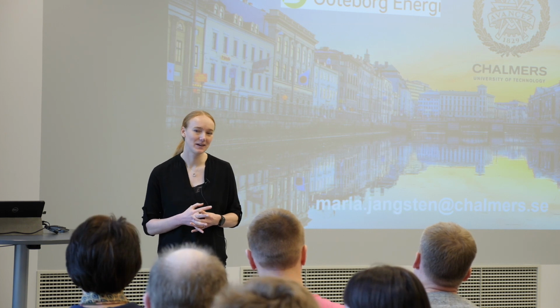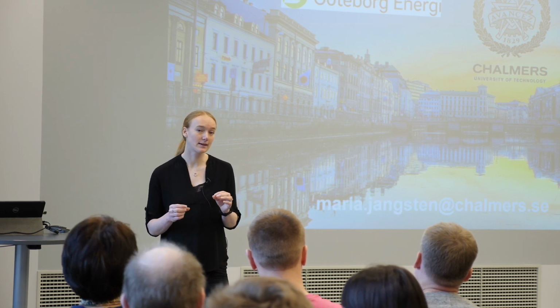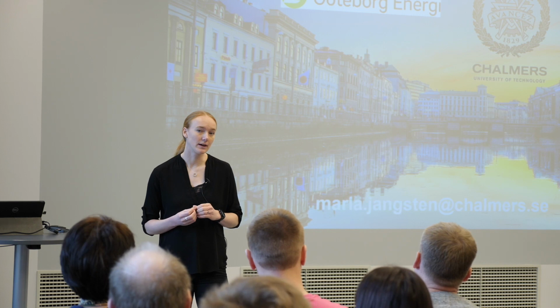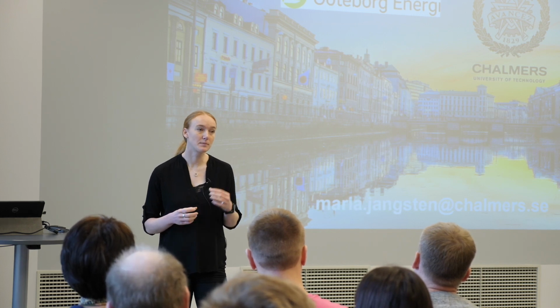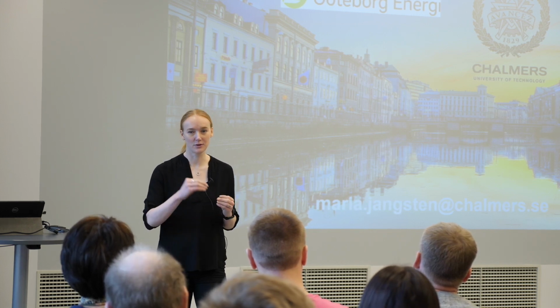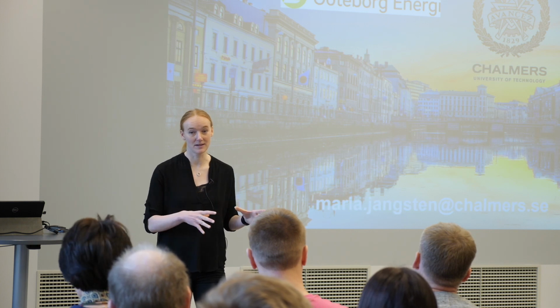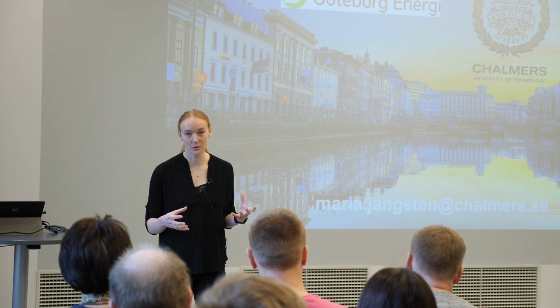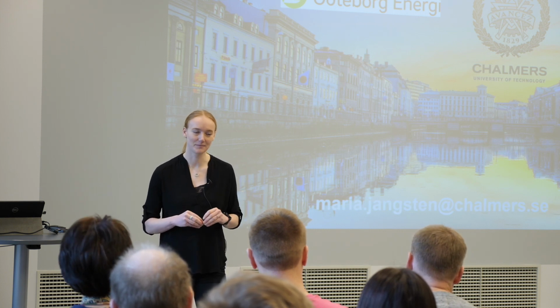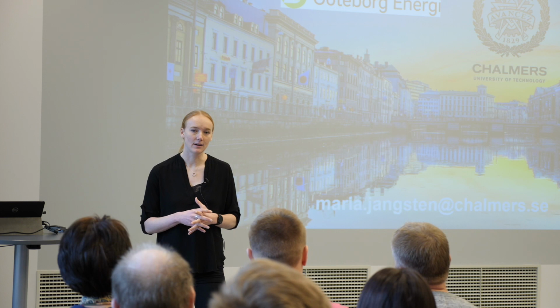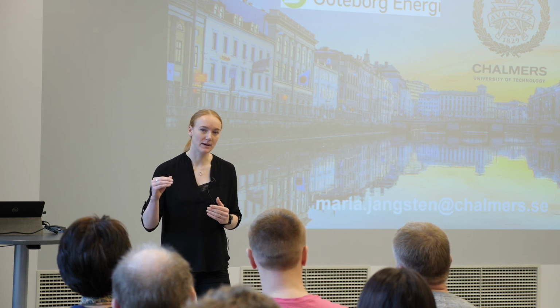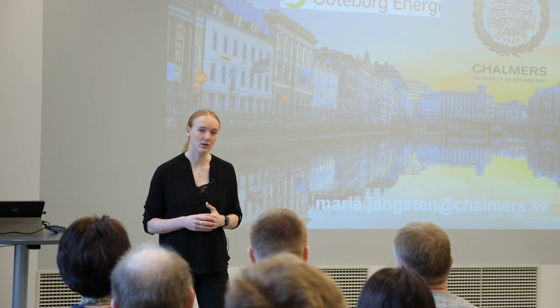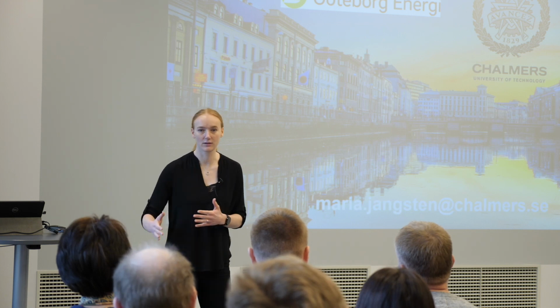Exactly, especially during spring. That's what I think the district cooling provider should do. In spring, the river temperature is slowly increasing, but the cooling demands in the buildings are still low, and the outdoor temperature is still fairly low. If they were to raise the supply temperatures in spring, they could use the free cooling for a longer period, so they can wait to turn on the chillers.